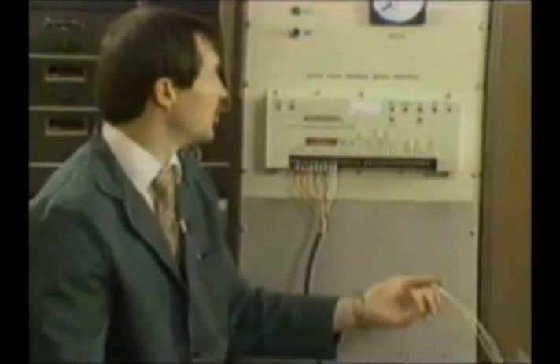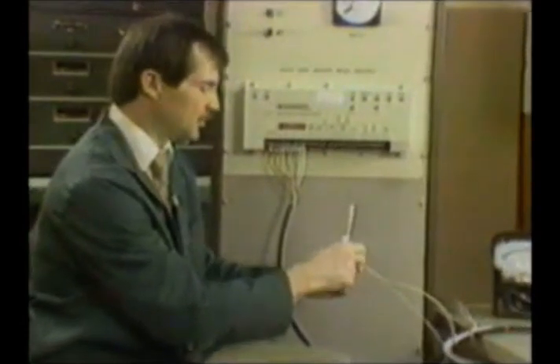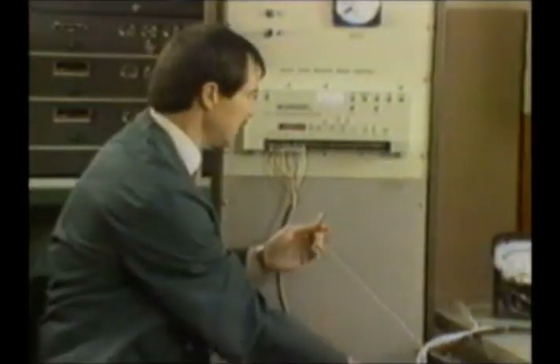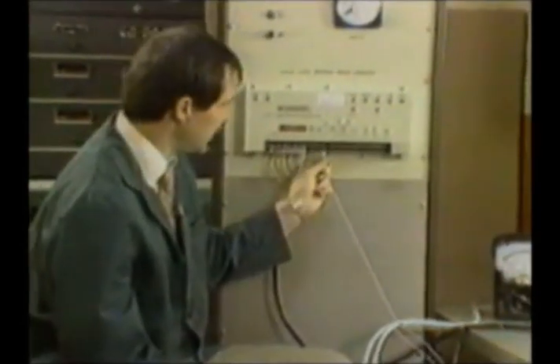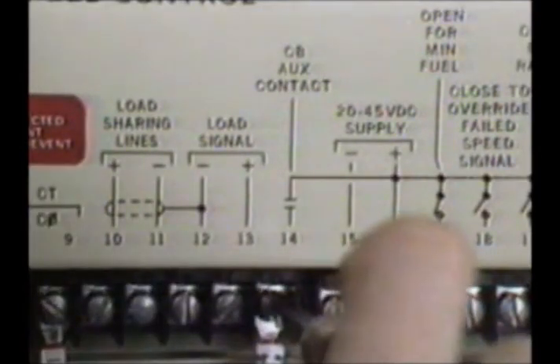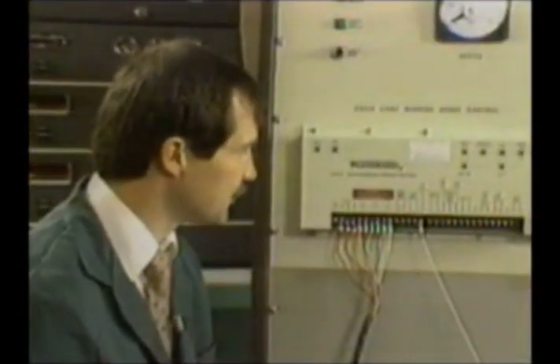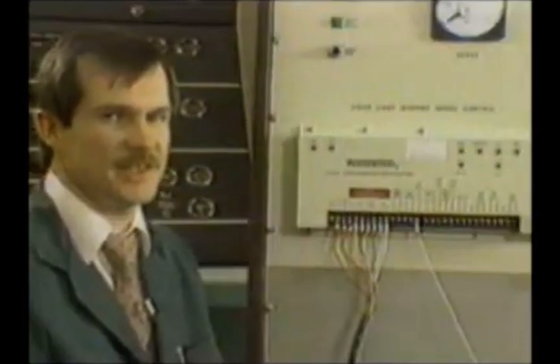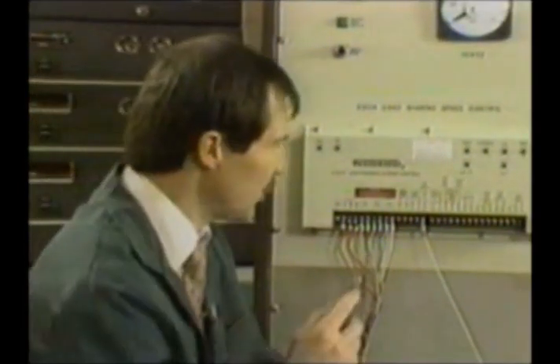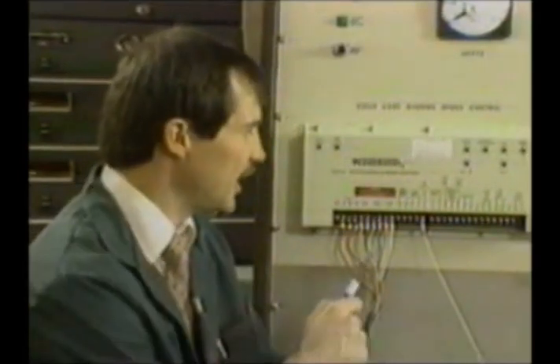Now, as I showed you earlier in my switch gear, we have a switch that I'm going to use to simulate terminal 14. Let me hook that up here. So I'll be able to close that switch and put voltage on this. I'll simulate a breaker closure. Terminals 15 and 16 are our power supply input, with terminal 15 being minus. As I told you earlier, the power supply input can go from 20 to 45 volts DC.